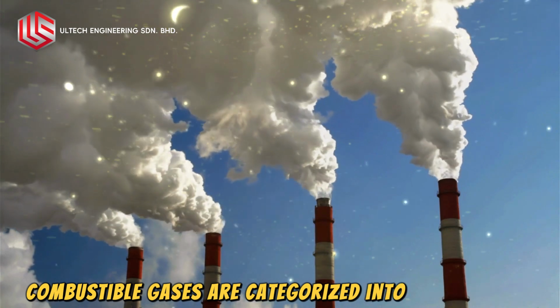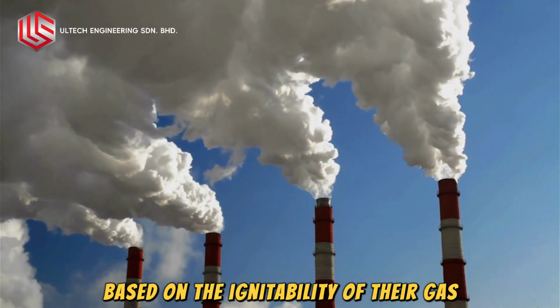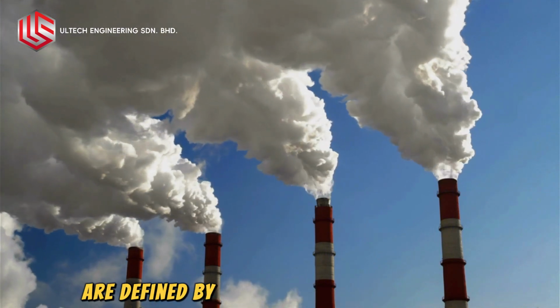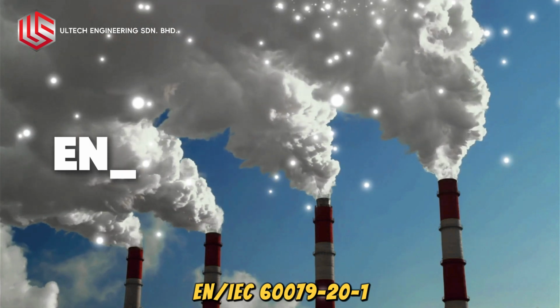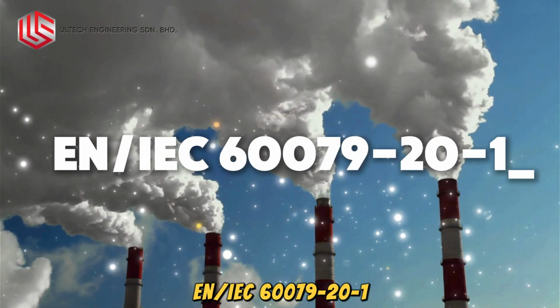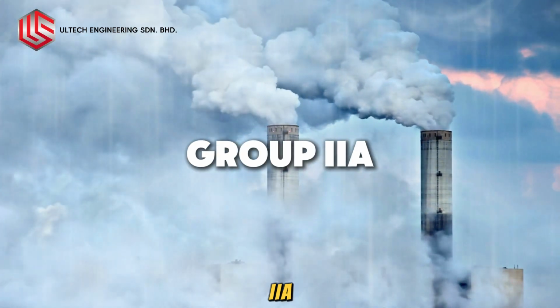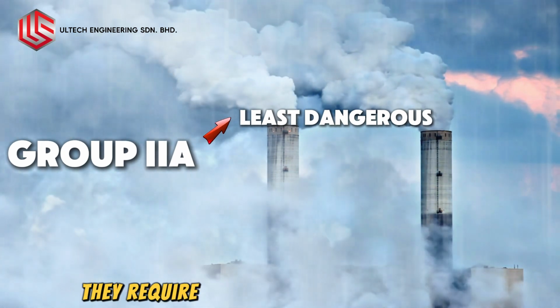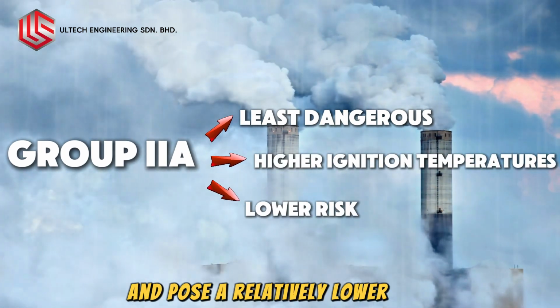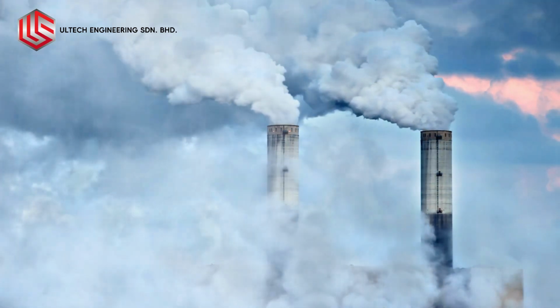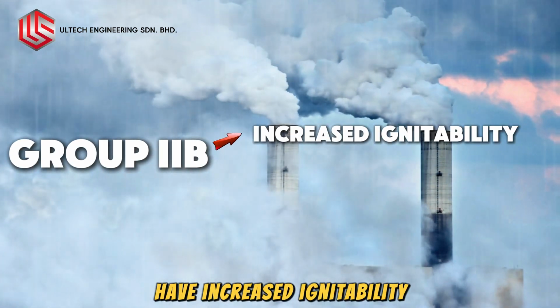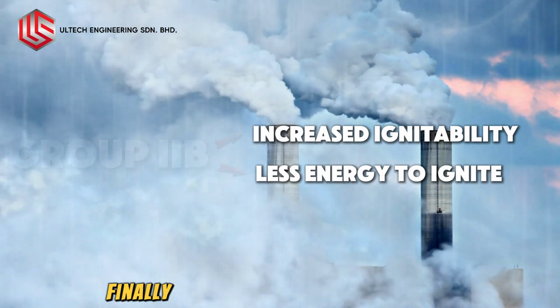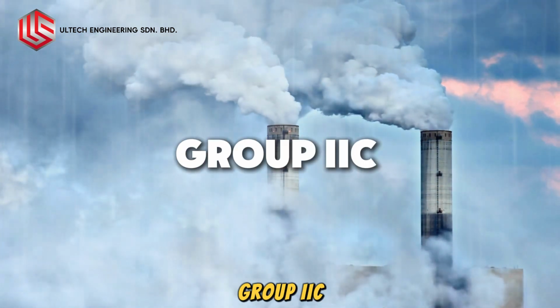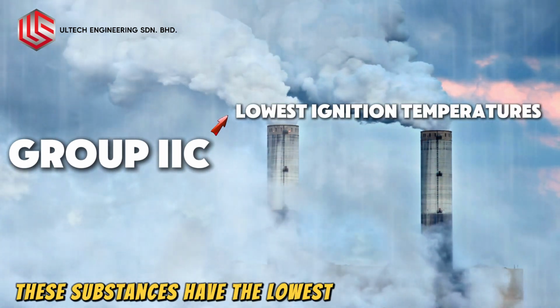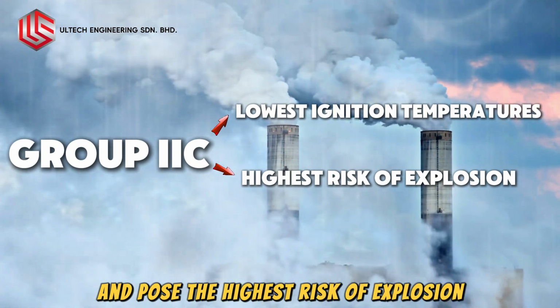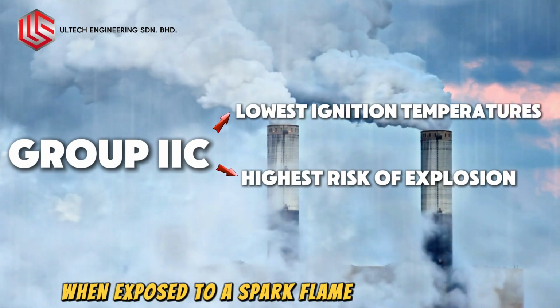Combustible gases are categorized into 3 groups based on the ignitability of their gas-air mixture. These classifications are defined by the international standard IECEx. Group 2A represents the least dangerous categories. They require higher ignition temperatures and pose a relatively lower risk. Moving up the scale, Group 2B have increased ignitability, requiring less energy to ignite. Finally, at the most dangerous end is Group 2C. These substances have the lowest ignition temperatures and pose the highest risk of explosion when exposed to a spark, flame, or heat source.